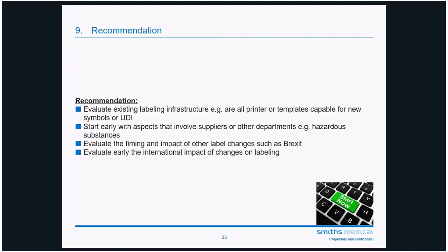A strong recommendation is that you evaluate your existing labeling infrastructure. Are your printers and templates all capable of handling those new symbols, or of printing UDI? If your infrastructure doesn't allow that, start as early as possible to replace and validate those, and to set the stage for the new MDR requirements. Also, I strongly recommend that you start early when suppliers or other stakeholders from different departments are involved. As I mentioned before, hazardous substances, for example, is a scenario where you may not be client A for your supplier, and that information delivery takes longer than you expect. So wherever other stakeholders, such as suppliers, are involved, keep that in mind.